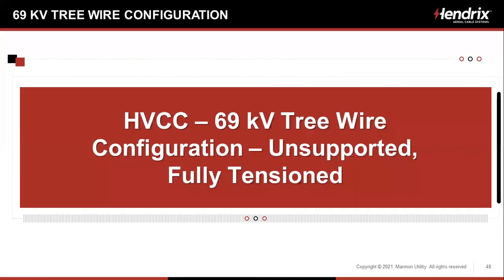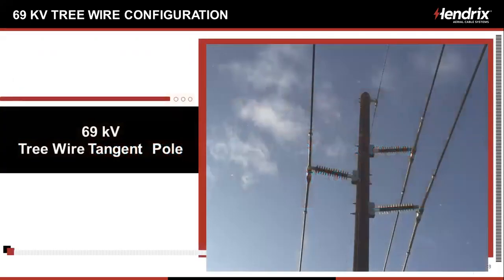So that's 69 kV spacer cable. How about 69 kV tree wire? We have a client in Canada that did not want to use spacer cable. They wanted to use tree wire. They weren't sure if spacer cable was yet approved by CSA. Today it is approved by CSA. This was several years ago. So they went with a tree wire configuration, fully tensioned. And they did a brilliant job.